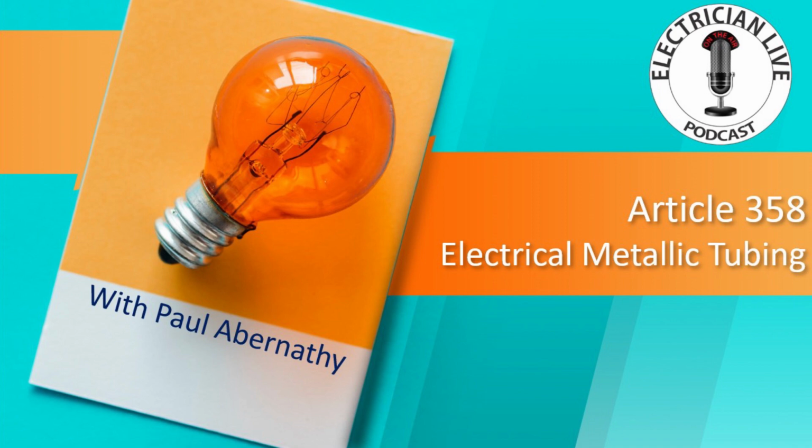Now, if I'm putting an NMB or an SER, or a tray cable, for example, inside of an EMT, I'm perfectly allowed to do that, because you saw back in our definition of EMT that it allows for conductors or cables to be in there. So it's perfectly fine, but you're going to have to treat that cable as if it's a single conductor.